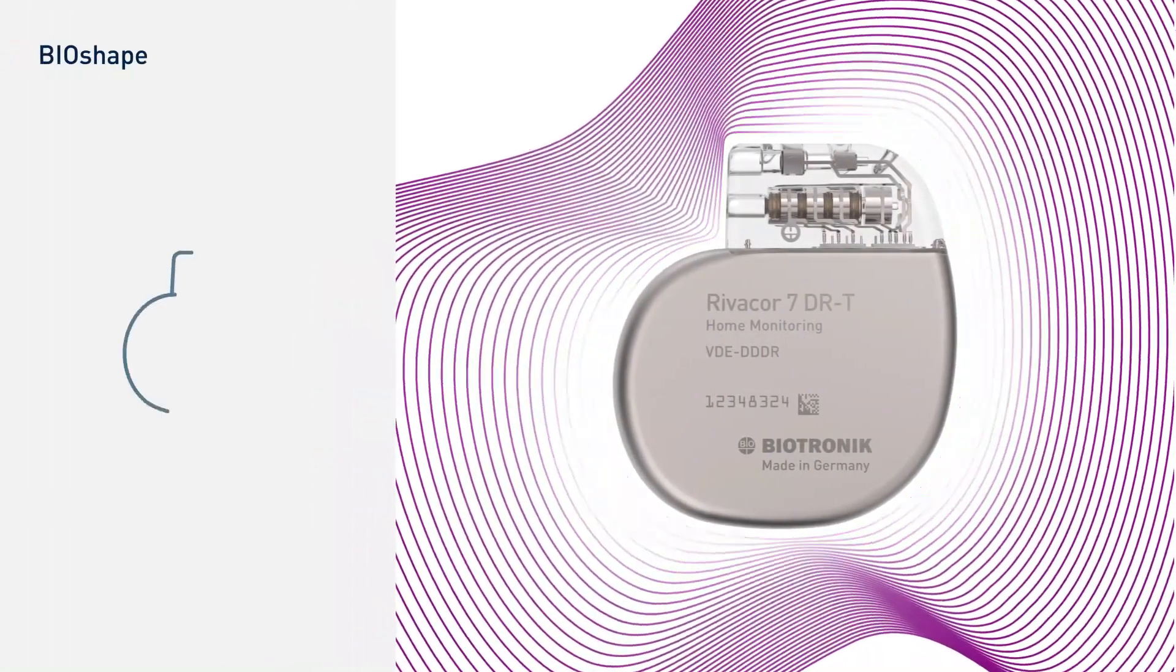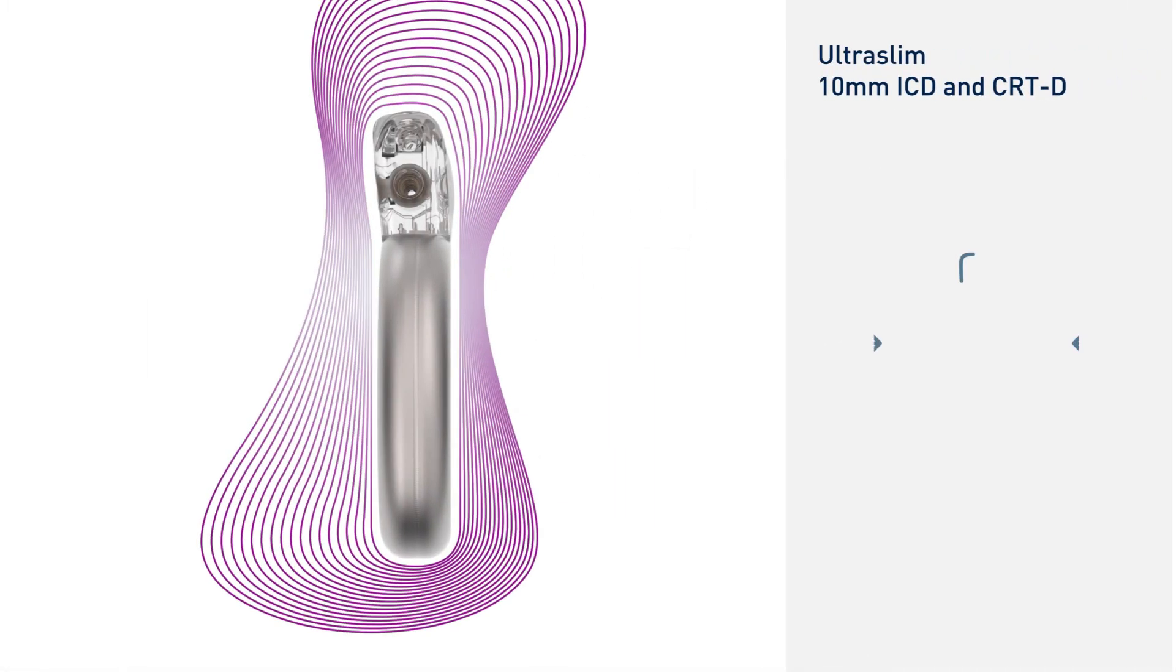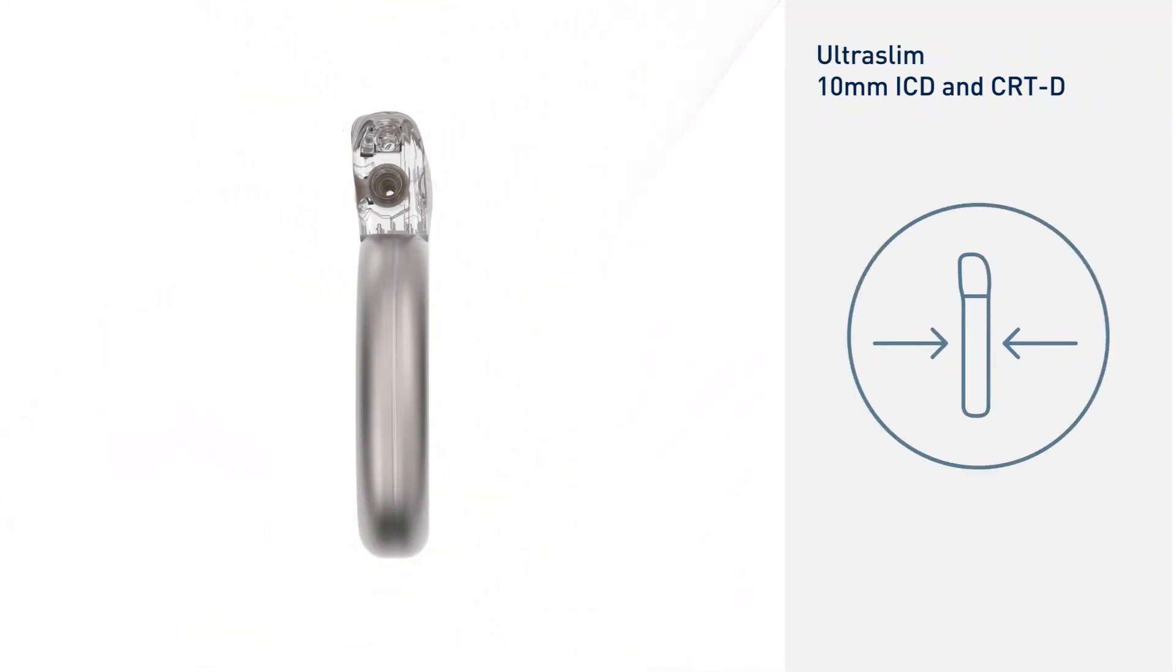ICDs, however, can stimulate the heart at a much higher voltage as compared to a pacemaker. The maximum voltage an ICD can achieve is 800 volts as opposed to 8 volts in a pacemaker system.